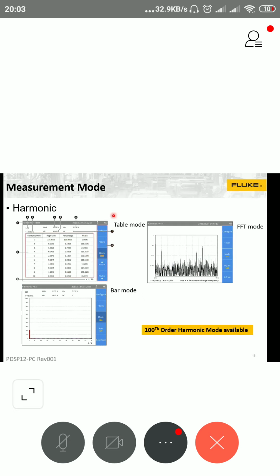Harmonics. Whenever we talk about power analysis, harmonics is one of the important quality measurements. Doing a harmonic study is very important to understand in which order there is too much harmonics presence and what necessary actions I need to take. This equipment has harmonics measurement, and it can measure up to the 100th order. Yes, you heard me, up to the 100th order. You can look at the numerical values, the bar graph, and also the FFT spectrum. All three are built into one equipment, and you can choose your scope and interest, whether it is the FFT or the numerical values.